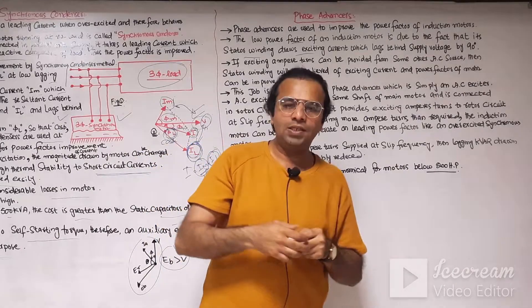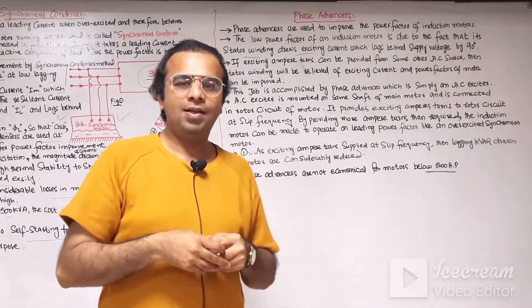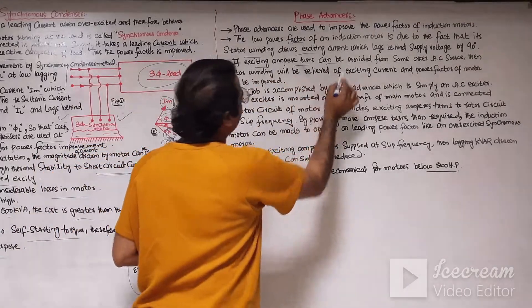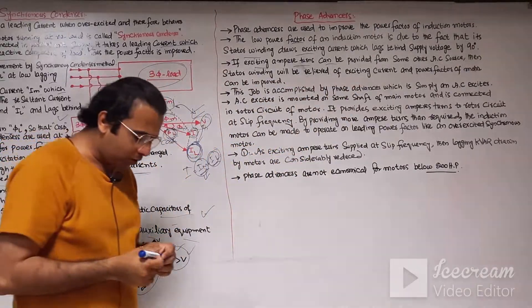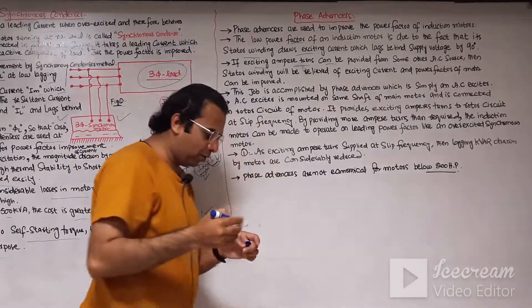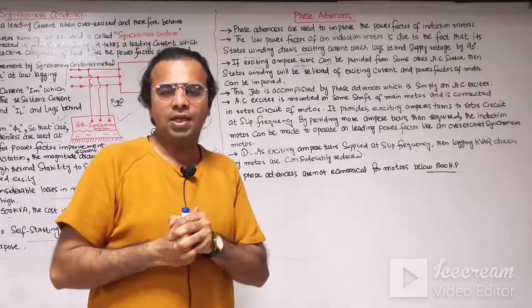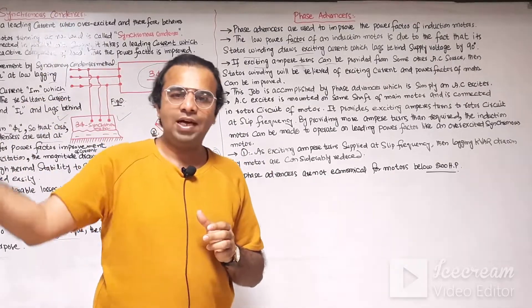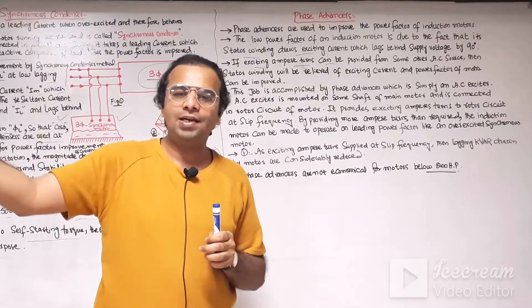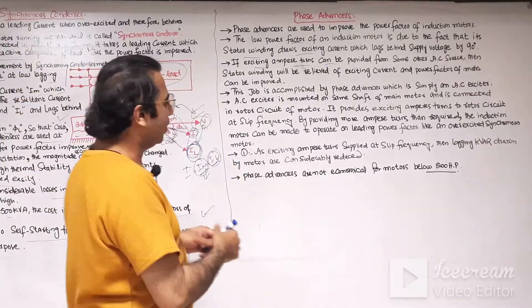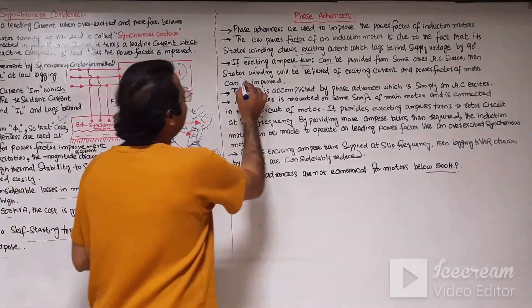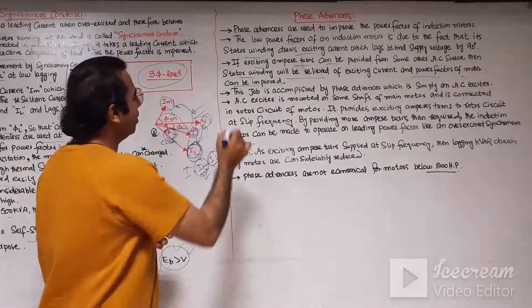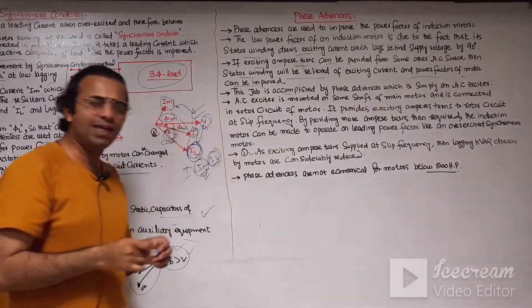The current drawn by the stator coils of the induction motor lags behind the voltage at 90 degrees. If exciting ampere-turns can be provided from another external exciter source — in the case of a wound rotor induction motor — if the slip rings of the three-phase wound rotor induction motor are connected to an external AC exciter and more exciting ampere-turns are supplied, the stator winding will be relieved of the exciting current and the power factor of the motor can be improved. This job is accomplished by the phase advancer, which is simply an AC exciter.